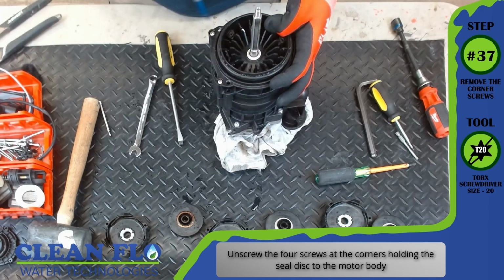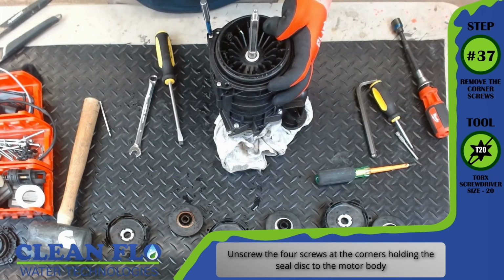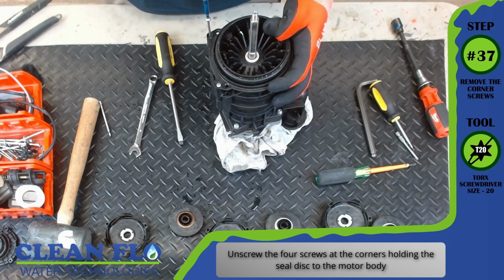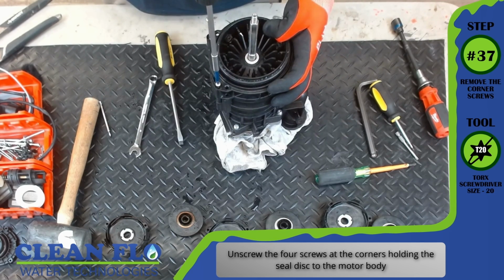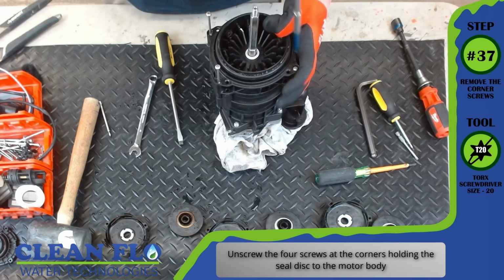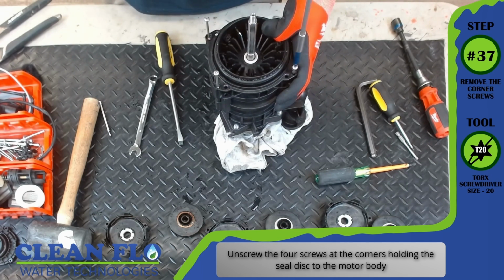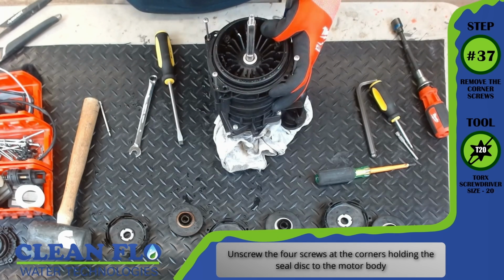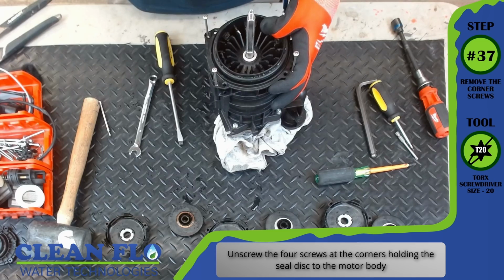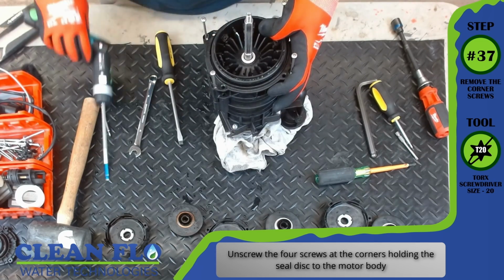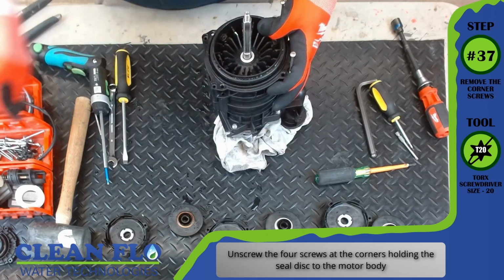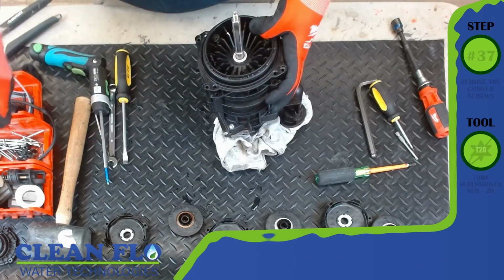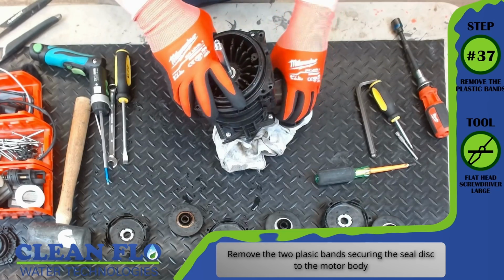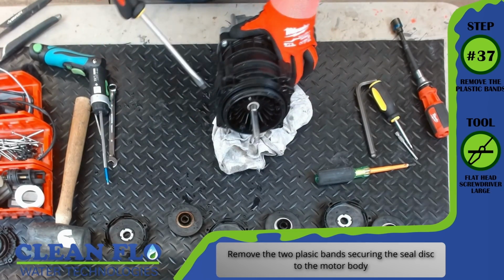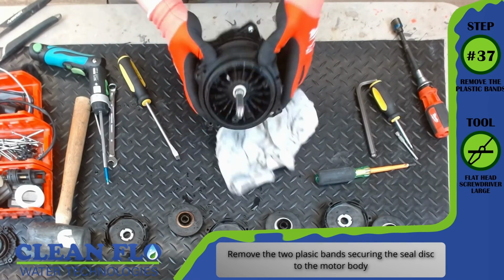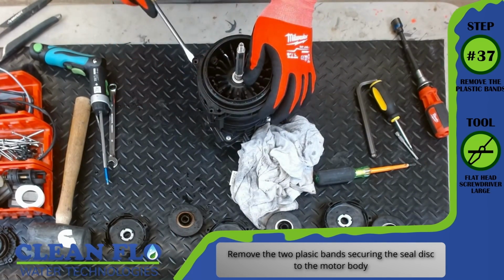Step number 37, remove the corner screws. Tool, T20 Torx screwdriver. Unscrew the 4 screws at the corner, holding the seal disc to the motor body. Continuation of step 37, remove the plastic bands. Tool, large flathead screwdriver. Remove the 2 plastic bands securing the seal disc to the motor body.